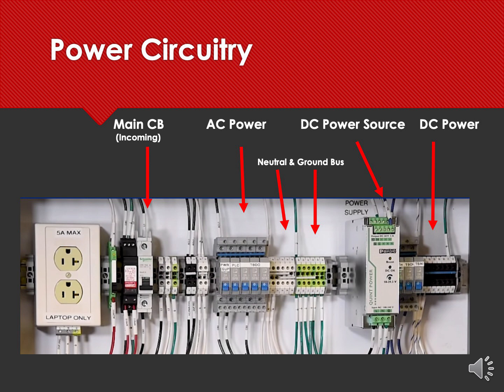Now, that arrow under the main circuit breaker is pointing to the incoming side of that breaker. It is very common to have three-phase 480 volt power on the source side of that breaker. And in fact, it can be high enough capacity that it could precipitate a significant arc flash. Further, there's often a transformer there where the 480 volts would be stepped down to 120 volts. And that then would be what you'd see coming into this panel. So it's possible that you could have, instead of a single circuit breaker, a transformer that has high enough capacity to precipitate arc flash hazards.